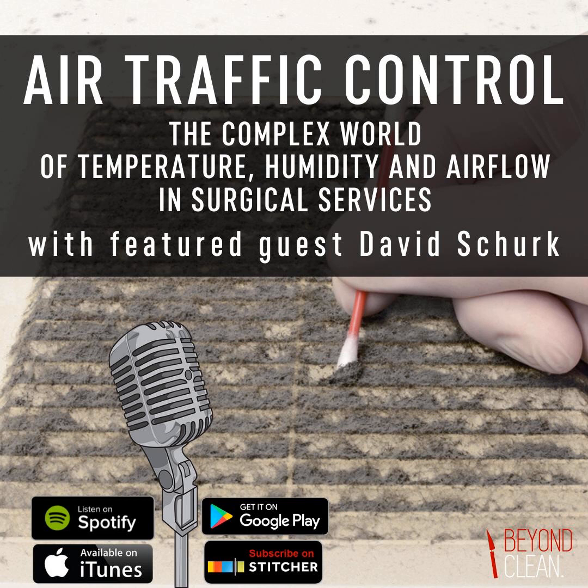I think it's just important, particularly with regards to the two instances we talked about most recently in Seattle and Dallas, where they're having mold growth issues in their ORs. I think it's very important in ORs and sterile processing that we be able to look at those temperature and humidity set points anytime we want to, and make sure that we have created an environment where condensation in the space cannot occur. So from a liability standpoint, I think we've just seen the tip of the iceberg with regards to what will be required from a compliance standpoint, from a measurement and verification standpoint. And I think you're going to see the facilities that are doing this haphazardly on their own have to step up and implement some type of building automation system that does continuous monitoring and recording all the time.